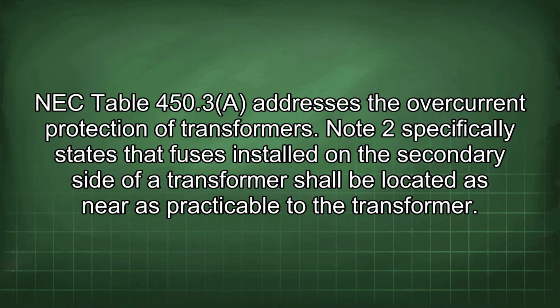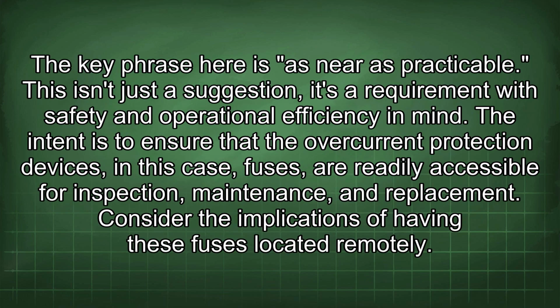NEC Table 450.3 addresses the overcurrent protection of transformers. Note 2 specifically states that fuses installed on the secondary side of a transformer shall be located as near as practicable to the transformer. The key phrase here is as near as practicable. This isn't just a suggestion, it's a requirement with safety and operational efficiency in mind.